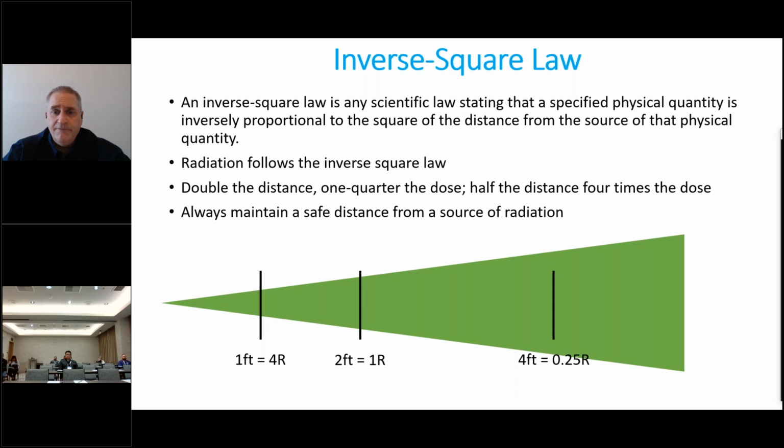If for some reason you need to be in an X-ray room while you're producing X-ray radiation, you should be at least 6 feet away, if not further. If you can be further away, you should be. There are very rare circumstances where we have to hold a device with a meter on it because we don't have a proper way to support it. In that case, we should be using sticks or brackets, and we should be at least 6 feet away from the tube.